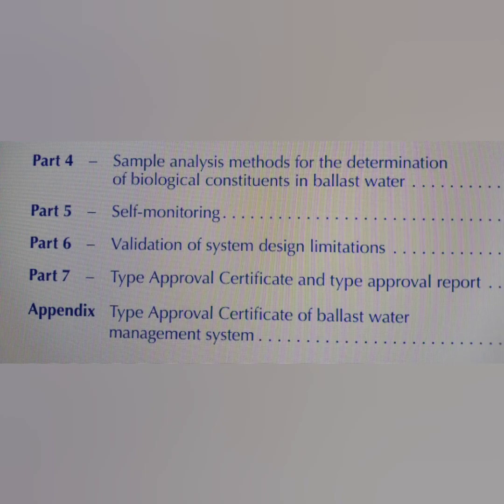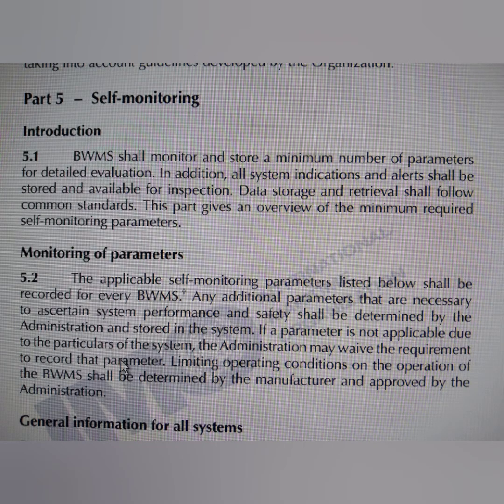Part 4 of the annex is about sample analysis method for determining biological constituents in ballast water. Part 5 is self-monitoring. The requirement is that the ballast water management system shall monitor and store a number of parameters for detailed evaluation. In addition, all system indicators and alerts shall be stored and available for inspection. This is similar to your ODME system — every kind of action that you perform on it must be recorded, whether you use it or test it.